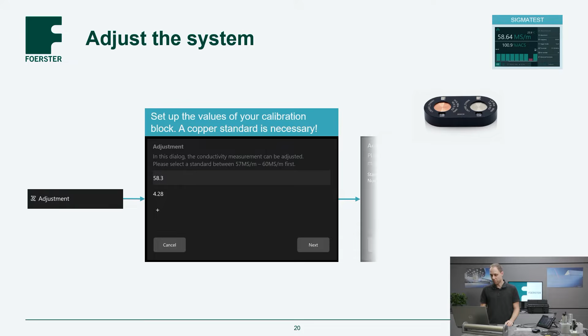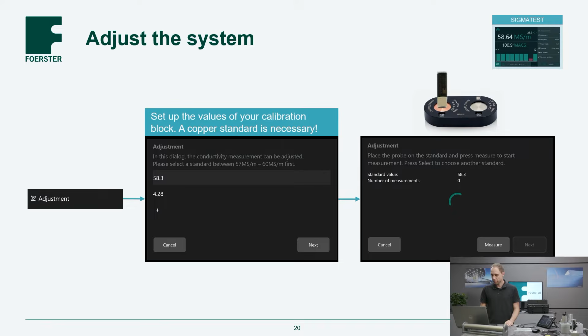Let's have a look at the adjustment of the system. For the adjustment, we can click on adjustment and set up the values of the calibration block, because for electrical conductivity measurement, we always need a calibration block. And for TCM sigma test, we always need a copper calibration block, a minimum. Then we do the measurement on this block, and our system is already adjusted. This we will also have a look at live later.